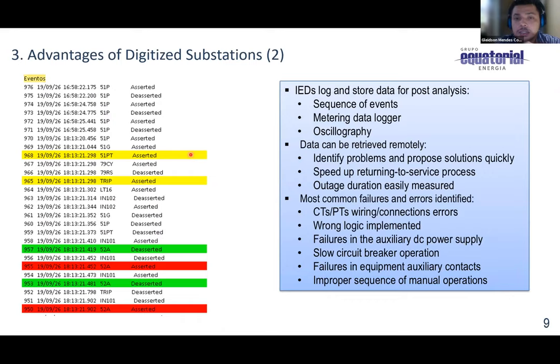They log all these internal errors, and we can check on this log. So the relays have a log function where we can see all the sequence of events, metering data loggers, oscillographies, and all this data can be retrieved remotely. Being able to retrieve this information remotely, we can apply solutions quickly. We speed up the return to service process, and outage duration is easily measured. The most common failures and errors we can identify on the logs are CT and PT wiring or connection errors, wrong logic implemented, failures in the auxiliary DC power supply, slow circuit breaker operations, failures in equipment auxiliary contacts, and improper sequence of manual operations.